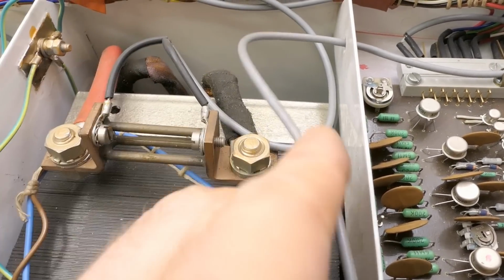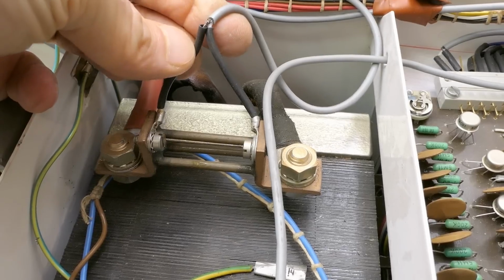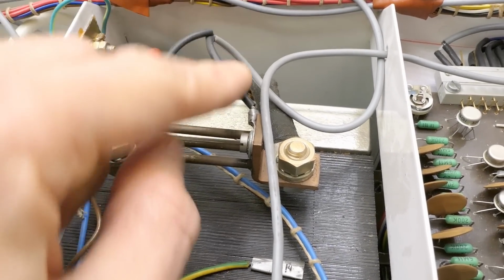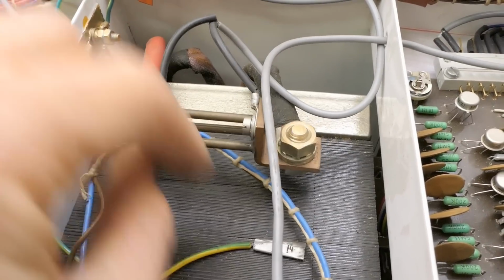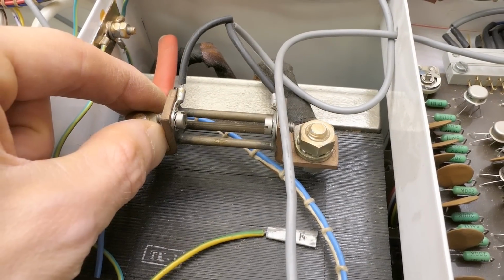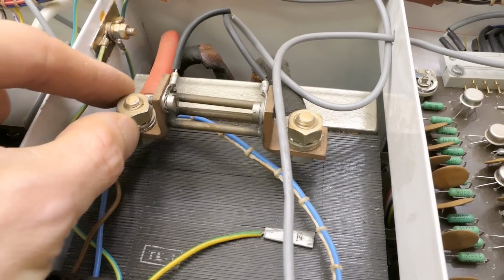This is sensing it. And again, this current sensing shunt has a Kelvin connection with two wires basically separately sensing the voltage drop and two other wires bringing the current into it. And this basically avoids measuring the resistance of the screw terminals.